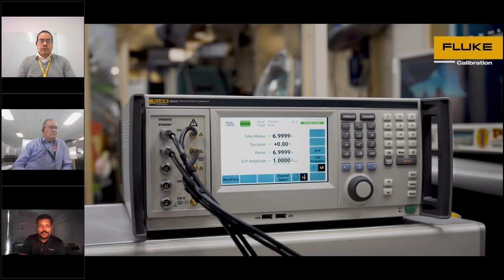It's really, the 9500C is really an outstanding machine. It is your key to exceptional signal performance. When calibrating oscilloscope trigger sensitivity, the dual sine output reduces the need for splitting cables, reducing total calibration time. You can easily switch between 1 megohm impedance and 50 ohm impedance and quickly match the impedance of your oscilloscope without any additional equipment, improving the automation capabilities. With the accuracy timing markers of plus and minus 0.25 parts per million, this reduces the errors while maintaining the level required to calibrate today's DSOs.